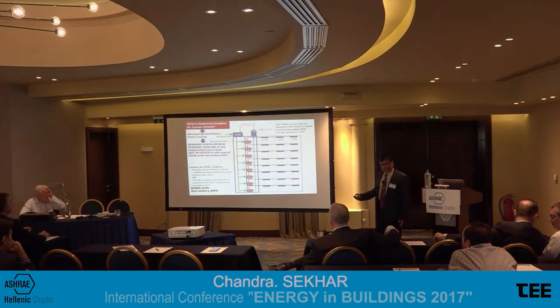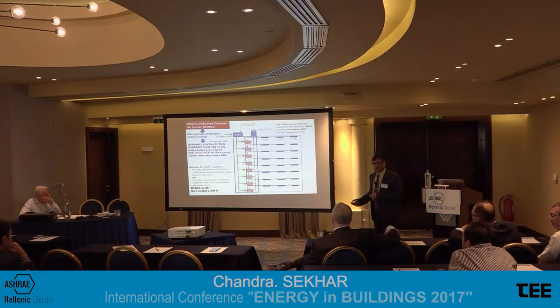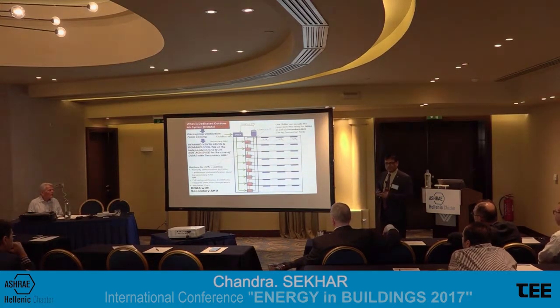In Singapore and a lot of cities in the Southeast Asian context, we have for a long time - not just recently with green buildings and the push toward providing better outside air - had this concept of taking outside air from a building's rooftop, doing some amount of cooling and dehumidification, and then supplying it to the local or floor-level air handling units.